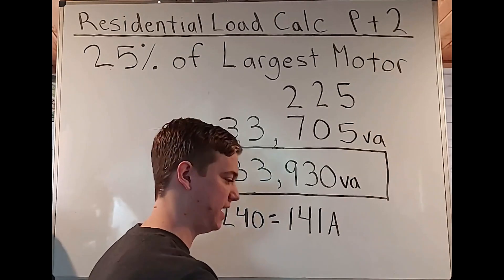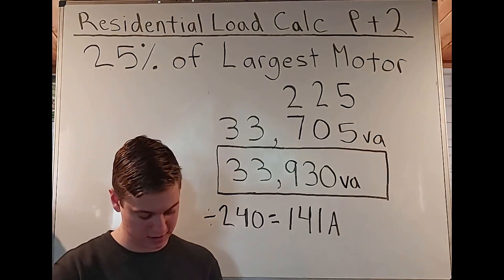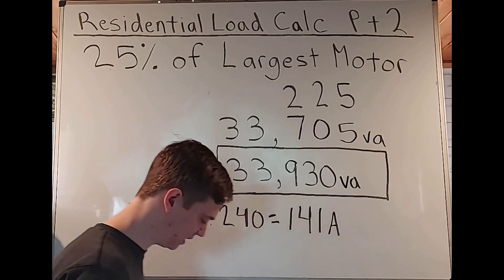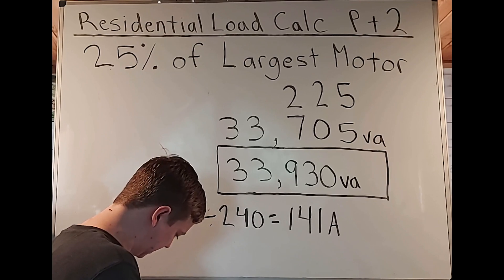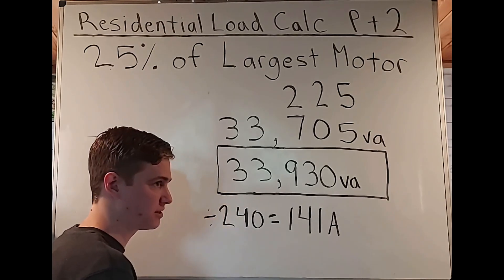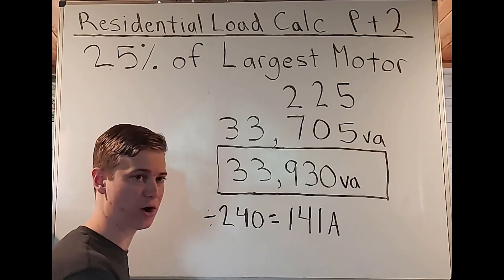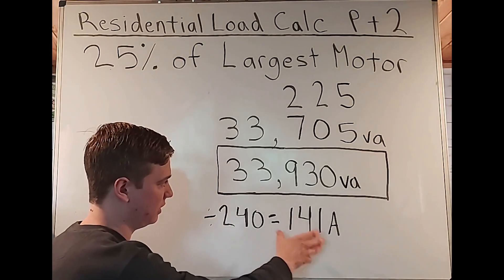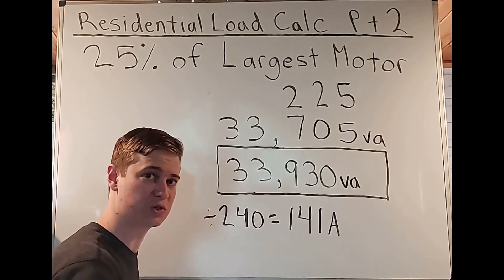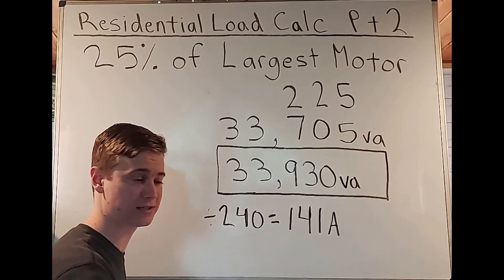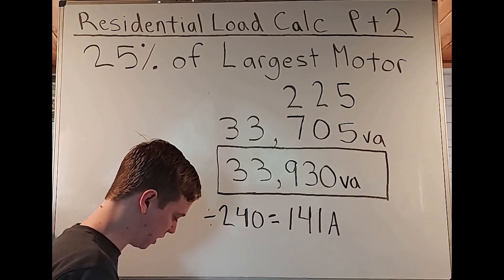So now that we have 141 amps, we can now go over to table 240.6A and find our standard amperage rating for fuses and inverse time circuit breakers. We see 125 and 150. Now we got to tell ourself and understand the fact that we're using a breaker here. So if we upsize the breaker, then we're saying that we're going to allow more current to be allowed to be supplied to those wires.